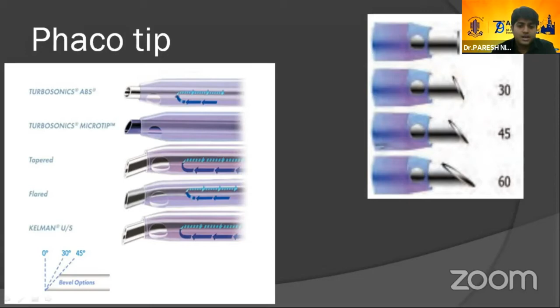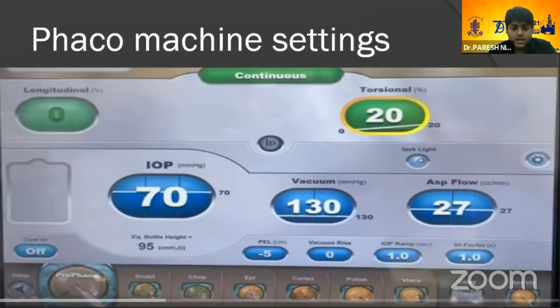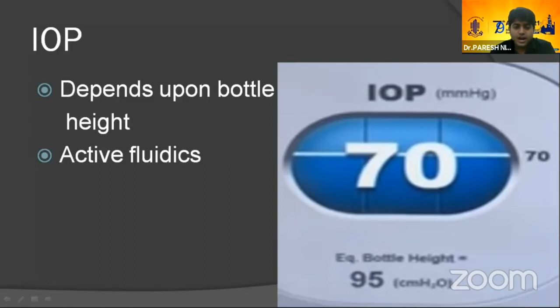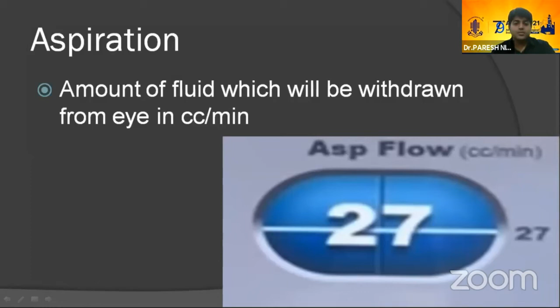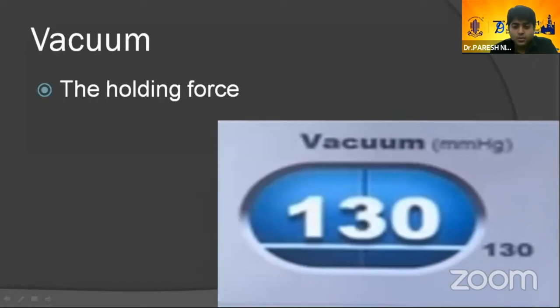There are different phaco tips available, with different shapes, sizes and angulations. They all have their advantages in different settings. Talking about the basic phaco settings, I'll be discussing the peristaltic machine. Basically, we can set the power. The IOP is dependent on the bottle height or the irrigation pressure, as in active fluidics. The aspiration can be set; it is basically the cc per minute withdrawal of BSS from the eye. And the vacuum is the holding force which we get.